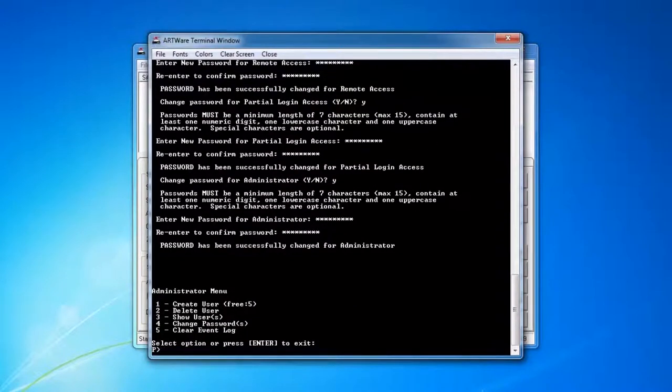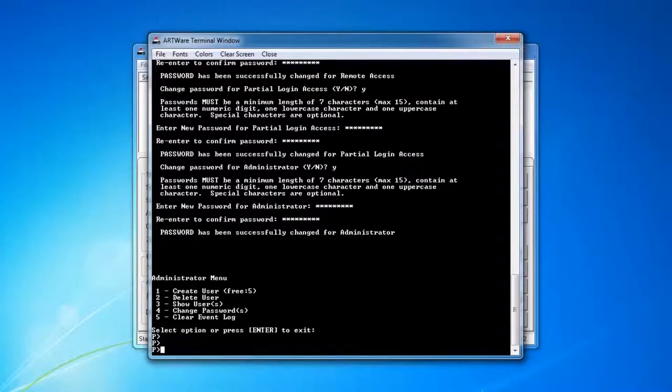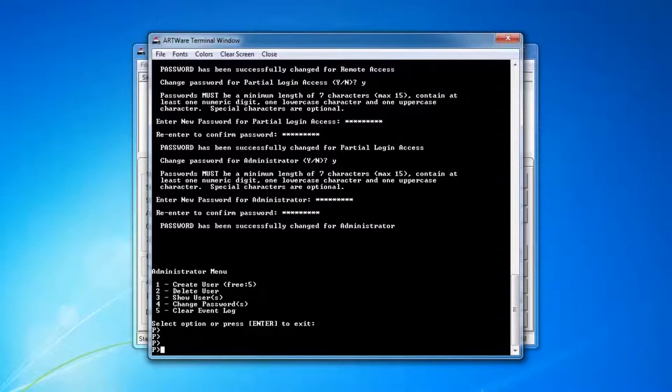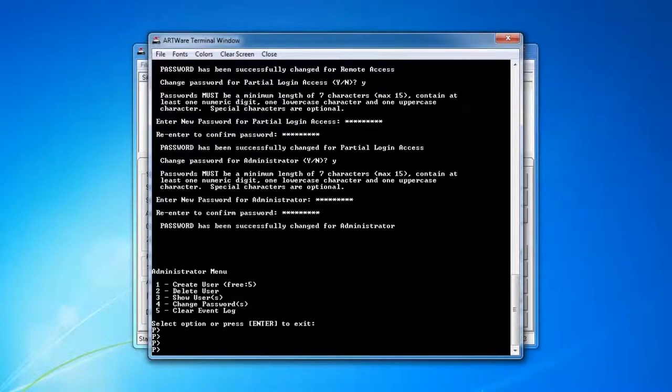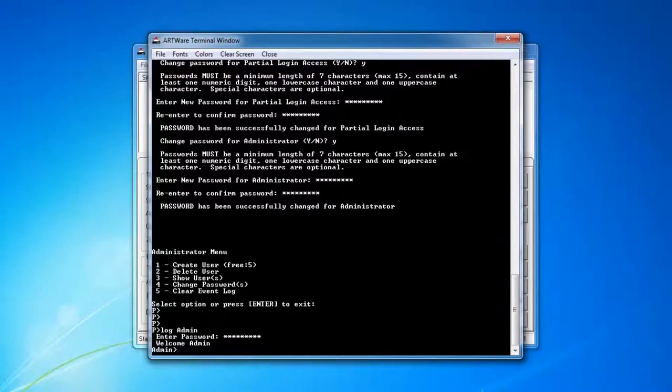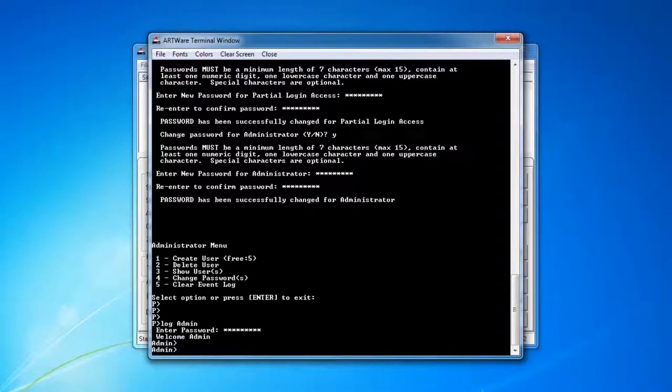And we are all done. You can go ahead and type in a new command to actually start the system so that the site can begin selling fuel again. That command is, once you log in to the administrator, you want to type in log admin with a capital A. Enter in that password you just put in. We are going to type system start.